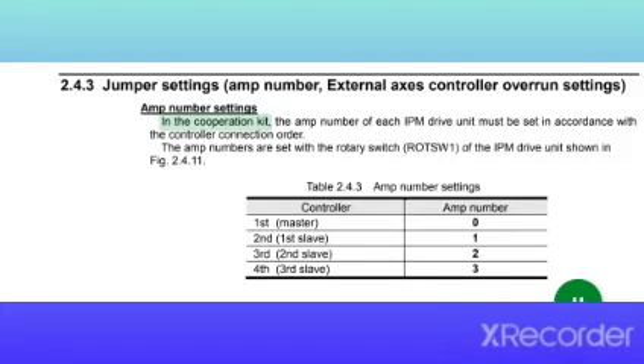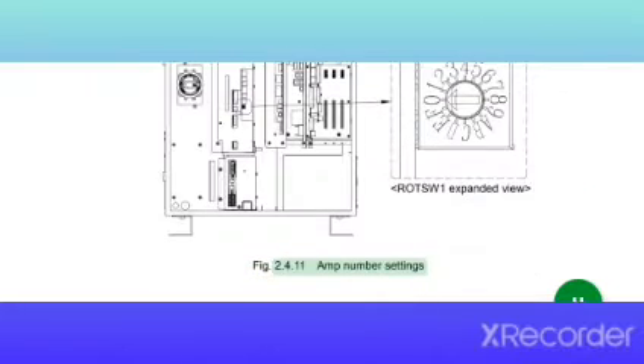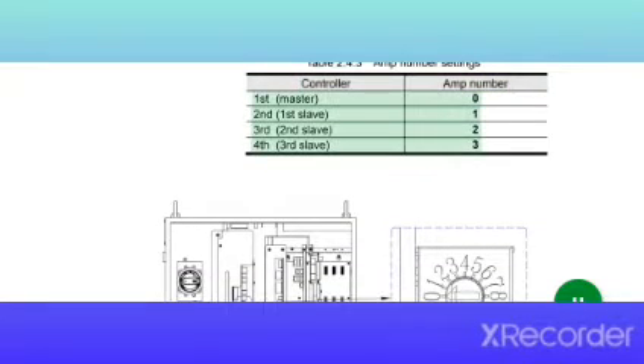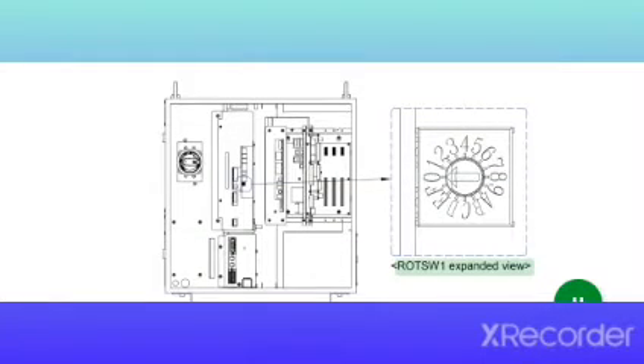In the cooperation kit, the amp number of each IPM drive unit must be set in accordance with the controller connection order. The amp numbers are set with the rotary switch ROTSW1 of the IPM drive unit shown in Fig. 2.4.11. Table 2.4.3 amp number settings. Fig. 2.4.11 amp number settings. Controller amp number: first master 0, second 1, third 2, fourth 3. ROTSW1 expanded view.